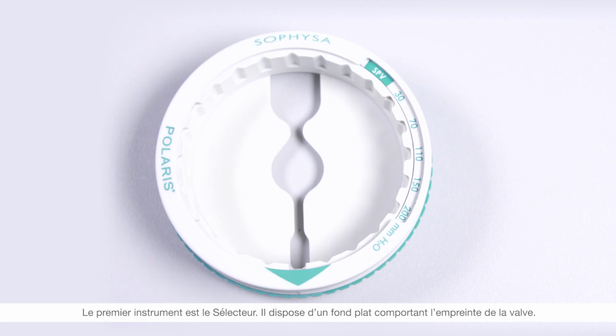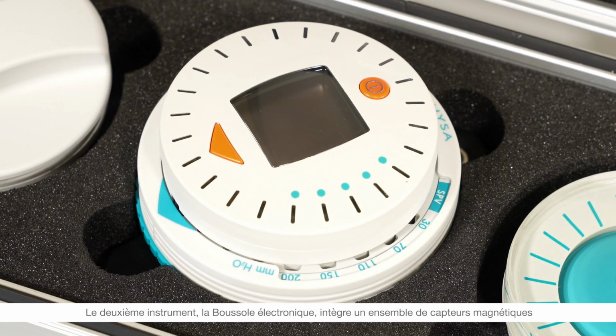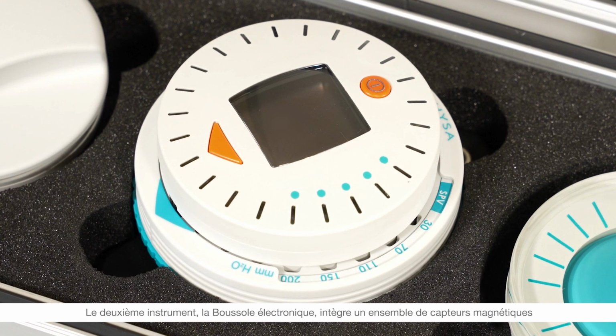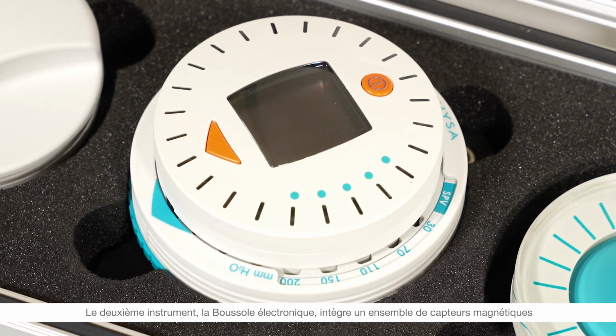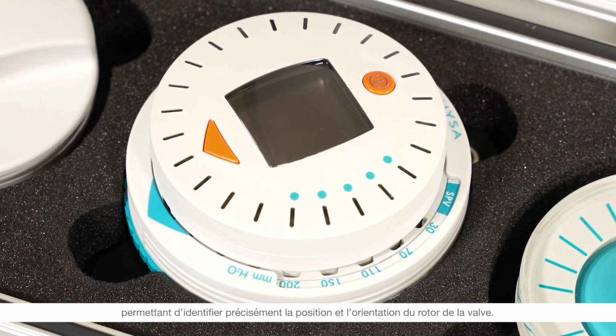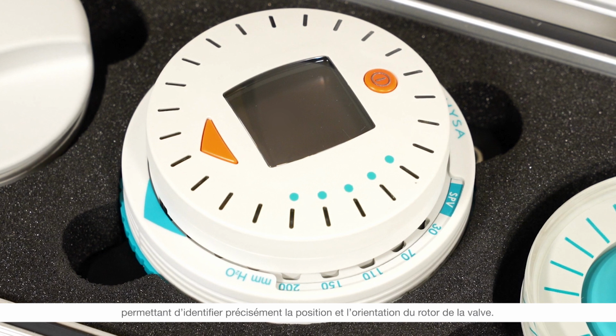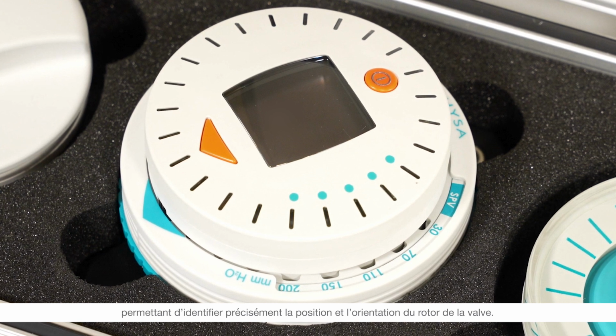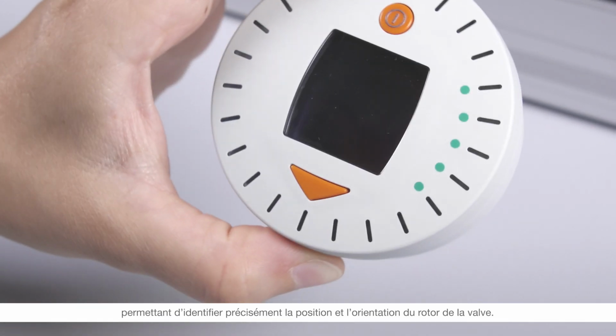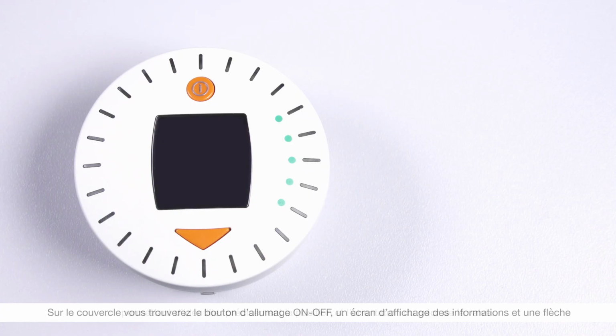It has a flat bottom with a cutout in the center in the shape of the valve. The rotating ring around the perimeter is used to select the pressure setting range of the valve being adjusted. The second instrument is the electronic compass. It has sensors that show the precise position of the implanted valve rotor and allow reliable and accurate direct reading of the pressure setting value of the valve.